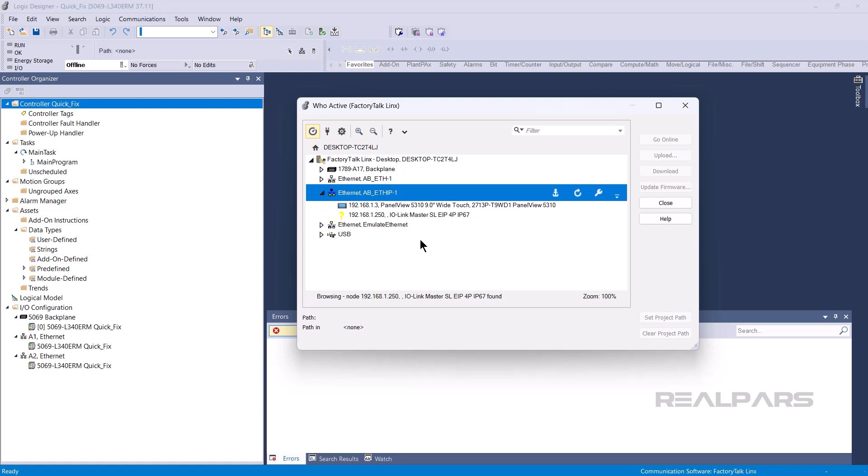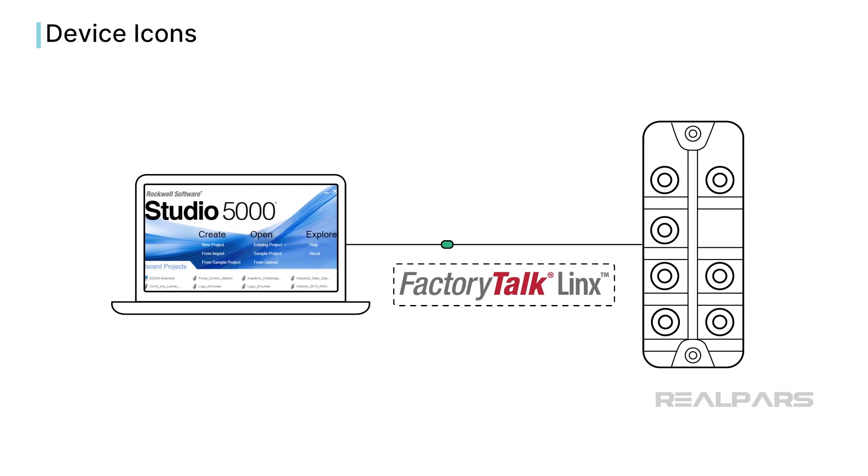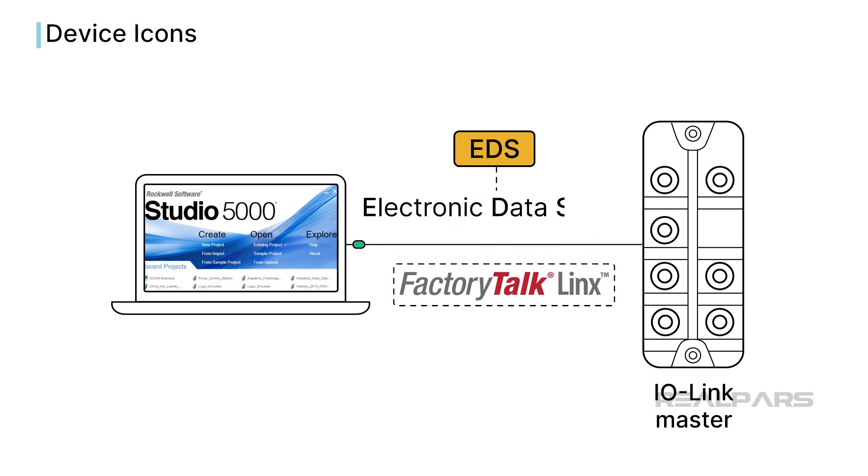Devices may also be shown with a yellow question mark. This indicates that FactoryTalk Linx has found a device but doesn't know how to communicate with it. This often happens with third-party devices. FactoryTalk Linx uses a file called an EDS or Electronic Data Sheet to define how it communicates with a device.